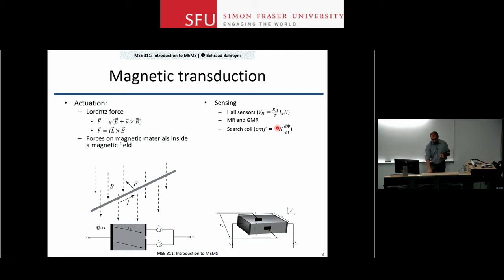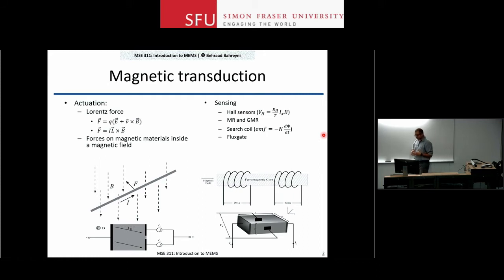Now, that's all good and it's a linear sensor, but you don't get a lot of signal out of that mechanism. What you can do is use a flux gate sensor. These are ingenious devices. The way they work is that you have a ferromagnetic core and two coils wrapped around this core. Normally, if you have a current through the first coil, you will pick up a signal on the second coil because of the magnetic coupling between the two coils, which is strengthened by the ferromagnetic core.